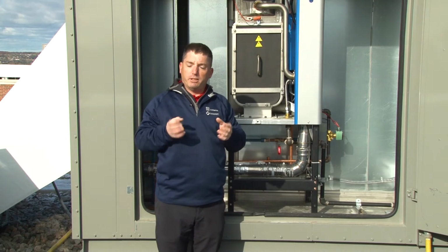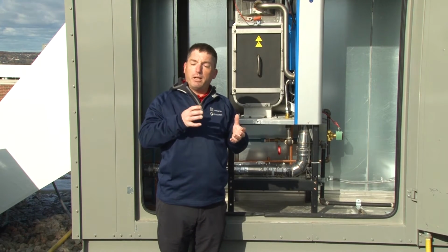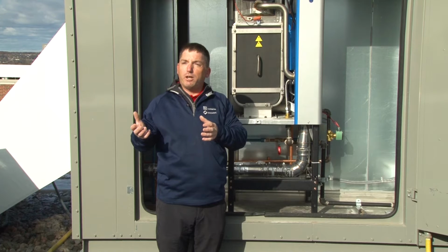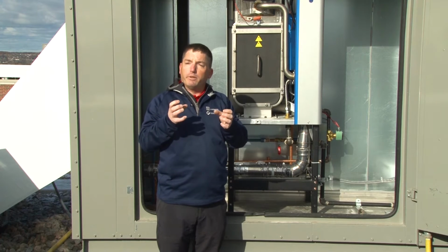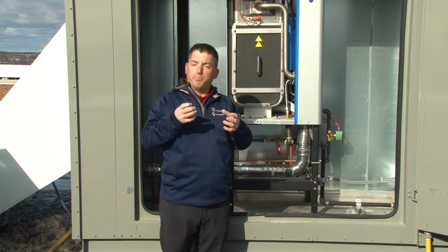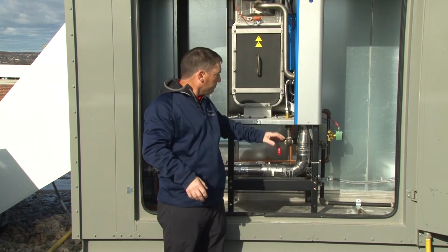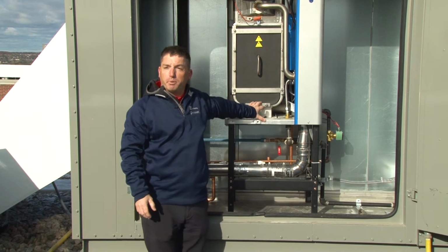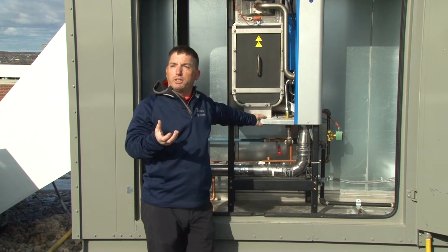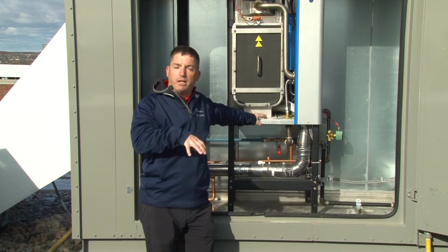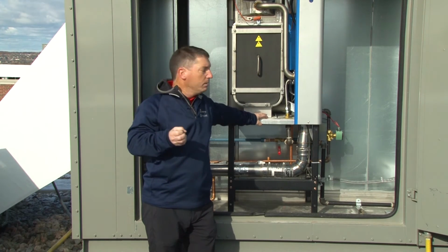During normal operation, between the time when it's running and the time when it's off, the heat exchanger is actually going to flex a little bit, which helps to break off some of the surface scale. So when you first open it, you're probably going to find some large chunks of scale in the bottom of the tank, which you can just take out by hand.